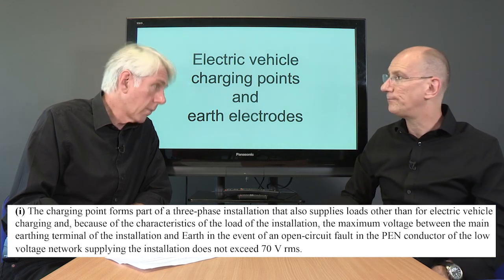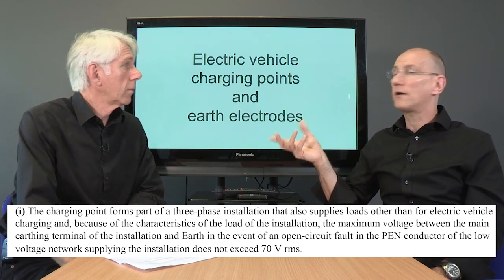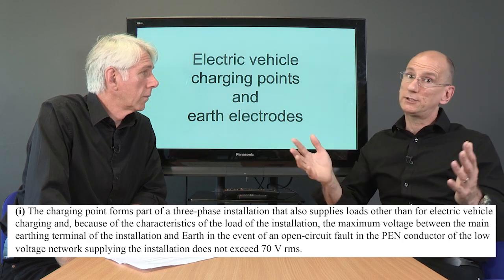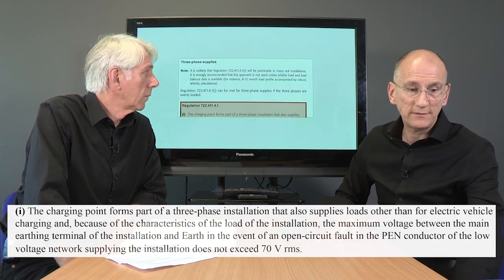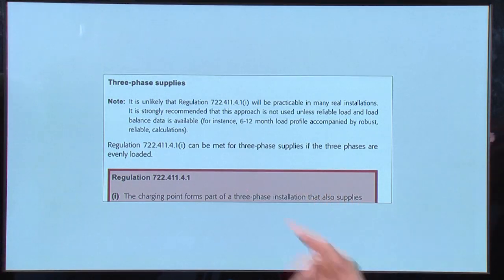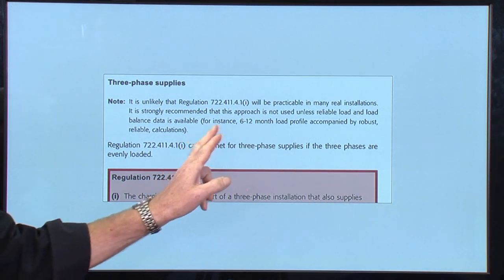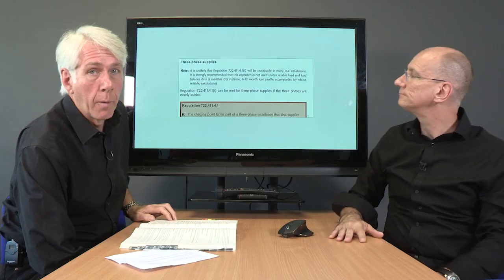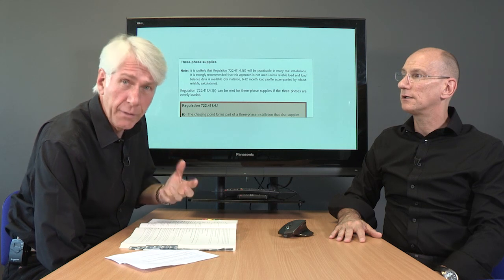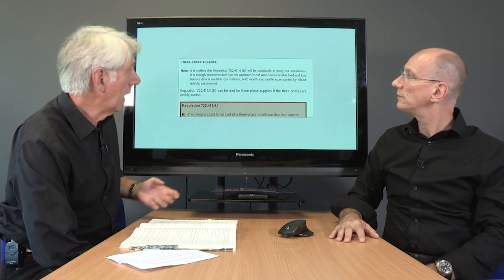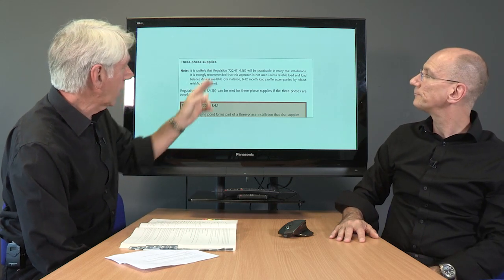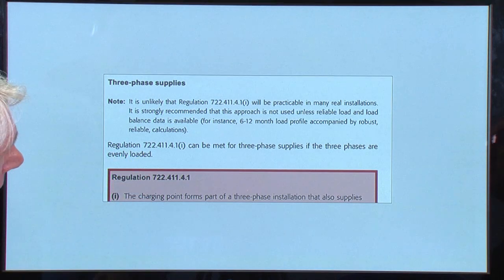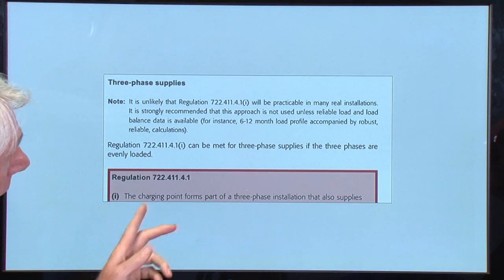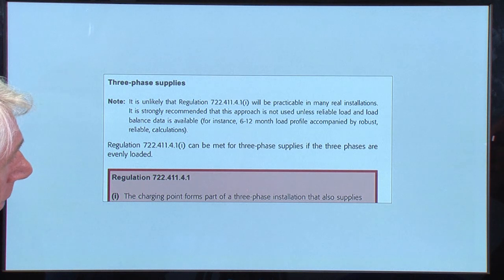And if you look at the guidance, this is the IET's Code of Practice, fantastic book and well worth getting. But even there, they make a note about three-phase supplies, because they're talking here about 6 to 12 months load profile monitoring, which in itself is going to be a difficult and expensive thing to do. Yeah. But even having made that comment, it says Regulation 722.411.4.1 Part 1 can be met for three-phase supplies if the three-phase supplies are evenly loaded. And again, we mentioned that as well. Yeah. Right, what's the second one?